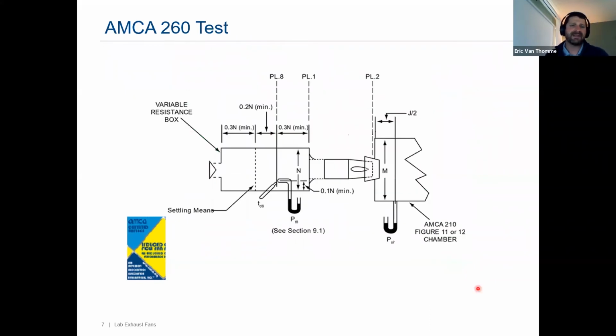I should mention that not all manufacturers participate in this certified ratings program. This is voluntary. And so when you're selecting and choosing lab exhaust fans, if you're looking for one that's got this induced flow capability, be sure you're looking for this AMCA certified ratings program label specifically for induced flow. This is really just a schematic of what the AMCA 260 test procedure looks like. You've got your induced flow fan blowing into the chamber in a variable resistance box. So what they're doing is they're measuring the inlet flow, and they're measuring the outlet flow, and then subtracting to come up with whatever that induced flow is on the certified ratings program.